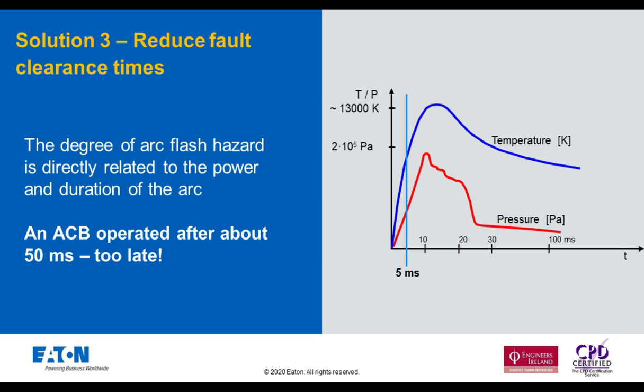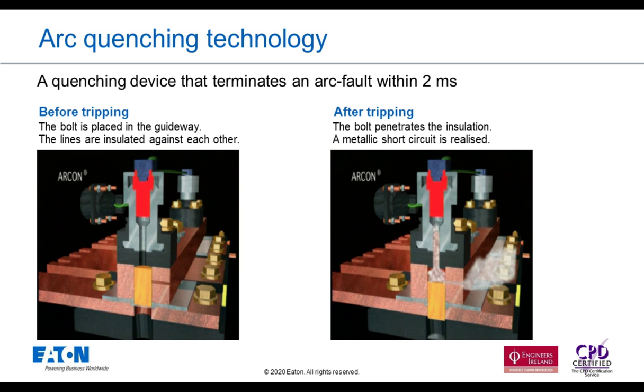And then there's also an IEC technical specification, 61439 Part 0, which is a guidance to specifying assemblies. Within that technical specification there's lots of additional information about arc faults, how they occur, why they occur, and ways to mitigate against them. So let's talk a little bit more about arc quenching technology. This is where an arc quencher is installed within the assembly to mitigate the energy supplying the arc, to quench it as quickly as possible.